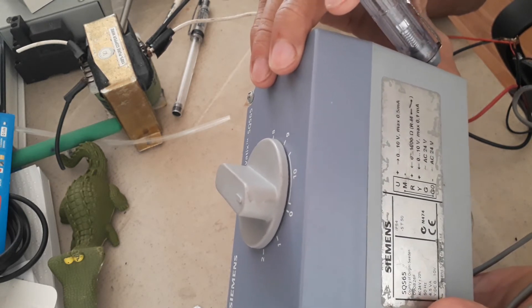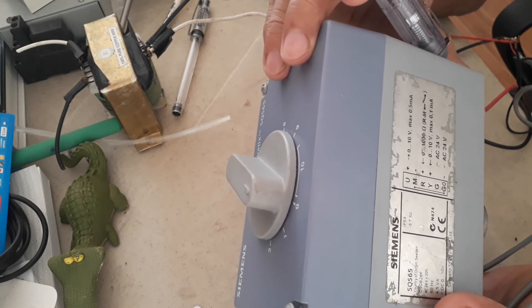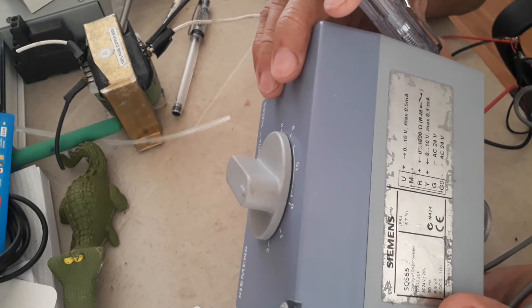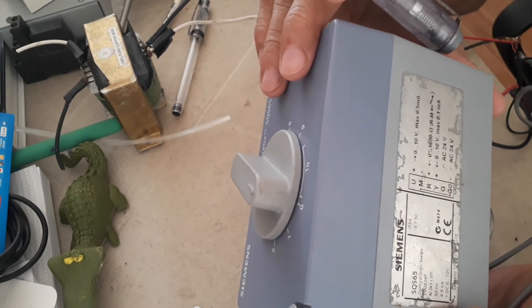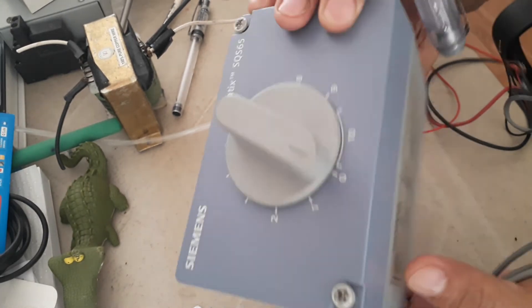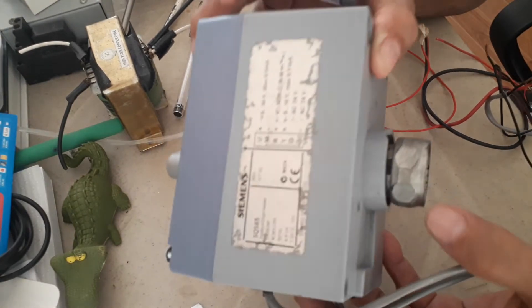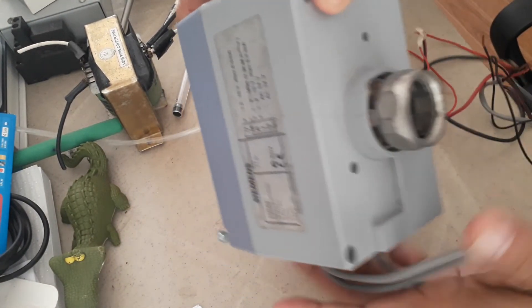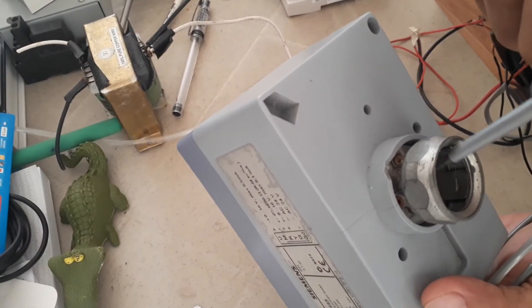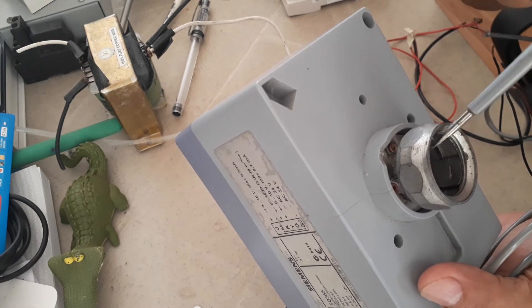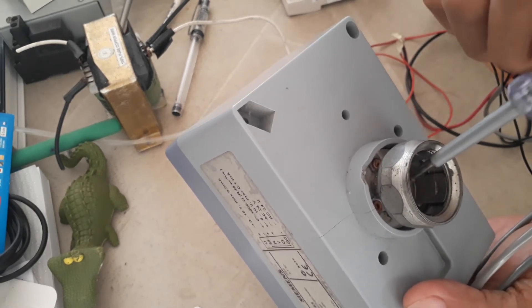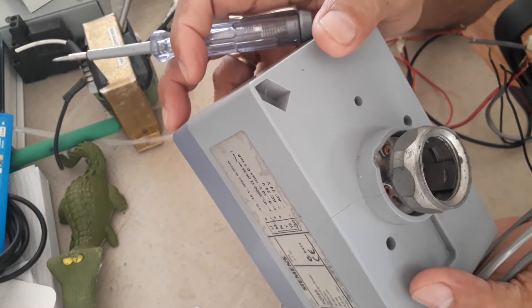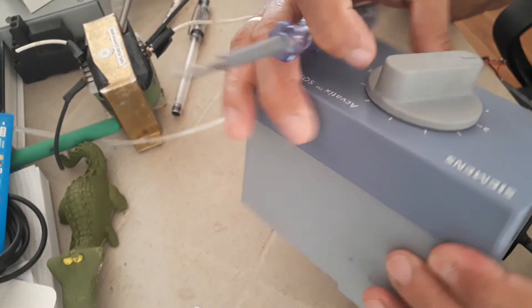The valve will be ordered by the mechanical engineer. Then, the valve actuator will be selected by the BMS engineer. But it is good practice that the BMS solution provider will be the one to select the valve and the valve actuator. The mechanical engineer of the project will give you the details of the air handling units, coil, the capacity of AHU, and the cooling coil capacity so that you can select properly the valve. This is the valve adapter, this is threaded. This is the one that pushes the valve stem to open and close. When it is opening, this one will push the valve stem to open also.